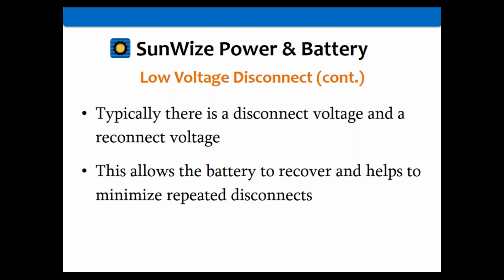One of the reasons to have a reconnect voltage is that if you were to reconnect immediately, it's just going to drop out immediately too, causing that load to go on and off, which is not good for the load, not good for the battery, not good for the system.